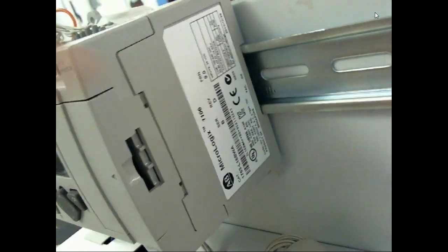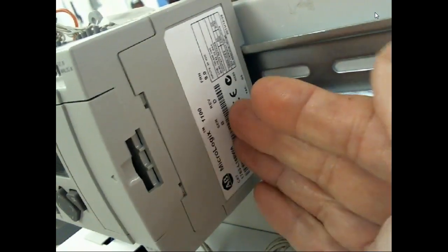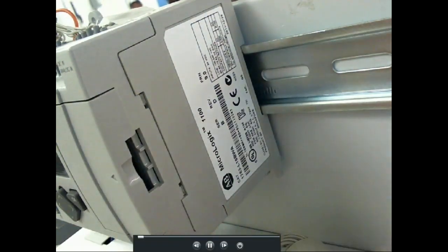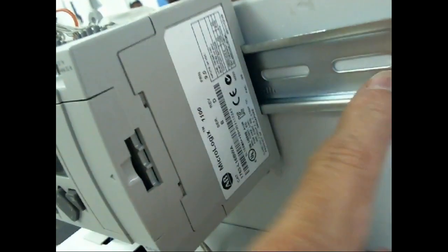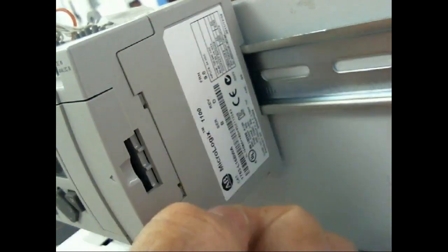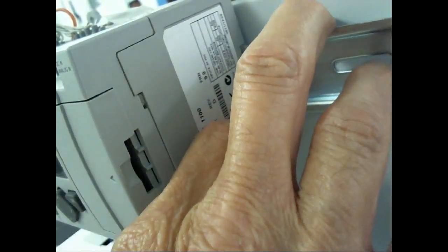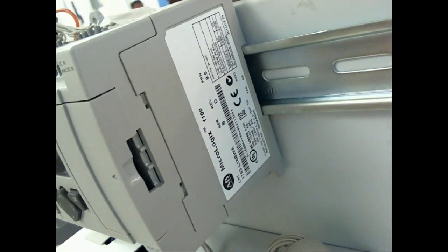So this thing has an access panel on the side over here, which is where we would take this off and then we could buy modules to plug into it. The backplane actually comes through the PLC itself. Are we okay? And this is designed to mount on a DIN rail. This is called a DIN rail. This is standard. You'll run into these all over the place. So we can take this off. It snaps on there. And we could put multiple modules. They would just daisy chain or plug into each other.